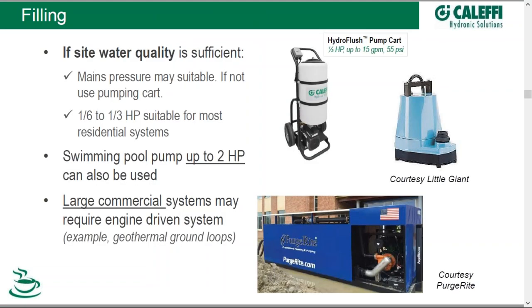If your water quality is sufficient, the pressure on site may be adequate to fill — no need for a pumping cart. But if not, use a pumping cart. There are many available in the marketplace: the Caleffi HydroFlush pumping cart, Little Giant, and big systems such as engine-driven systems like PurgeRite are also available. For smaller jobs, pumps of one-sixth to one-third horsepower are typically sufficient; even a swimming pool pump up to two horsepower can be used.